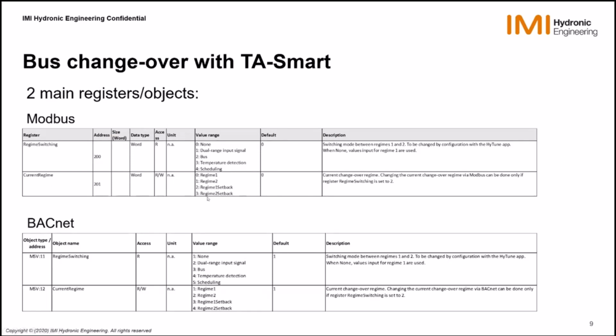And then there are 2 additional ones that we will use later on. About at the same time as we come with the scheduling, we will introduce something more, which is the setback on regime 1 and 2. Imagine that we are in heating and cooling. The setback will be a way, by scheduling, to define that at a certain time of the day, you want the valve to apply only a fraction of its maximum flow. For instance, you could take a setback at 80%, or 70%, or 50% of the normal max flow. That could be a way to simply decrease the heating and cooling overnight, for instance, through the power control, or possibly you may prefer through the flow control.